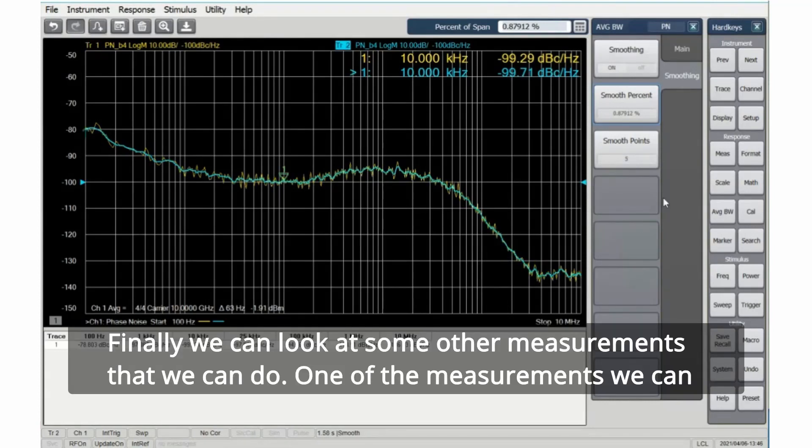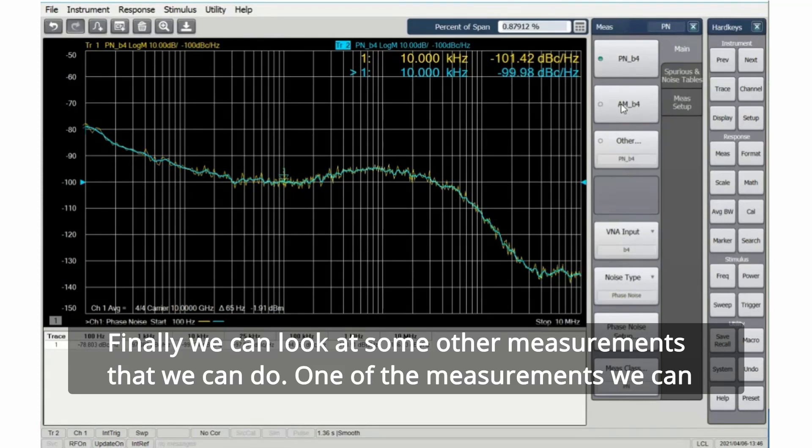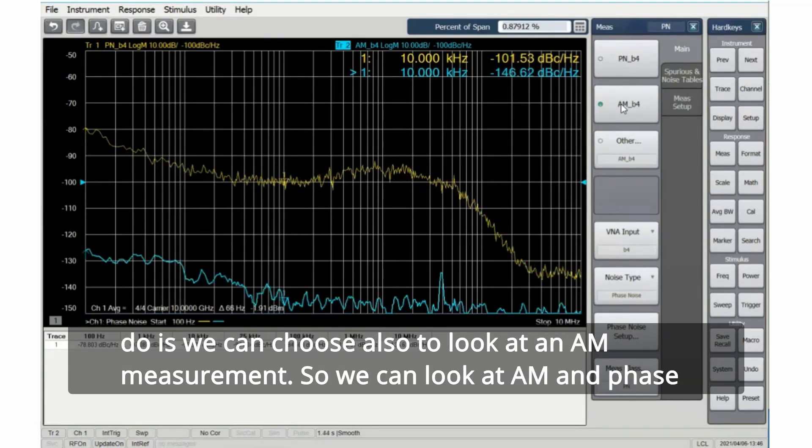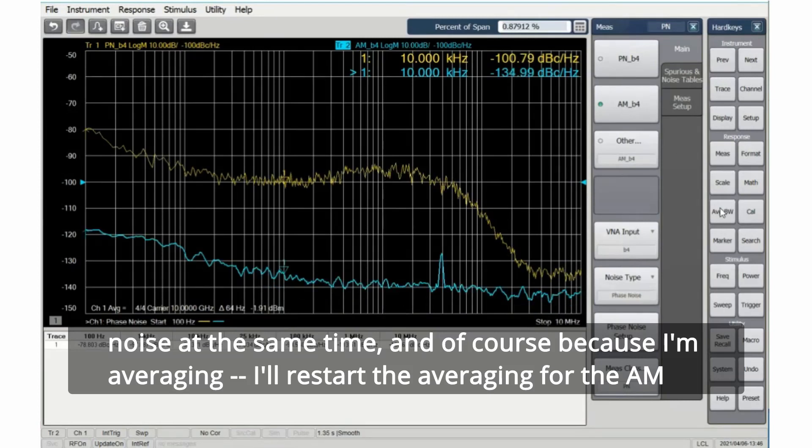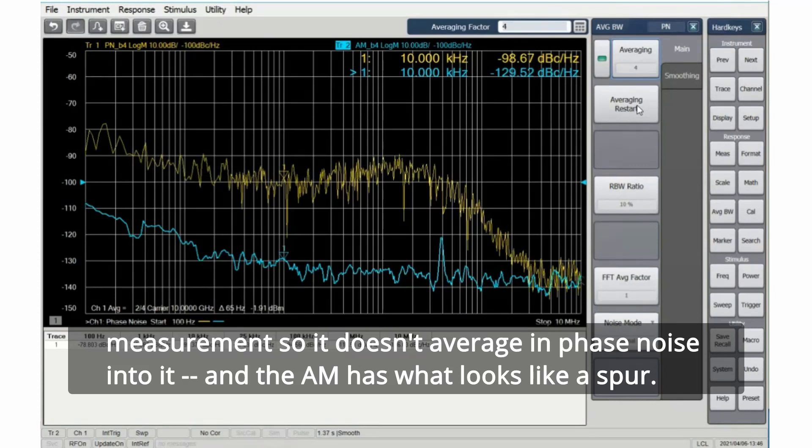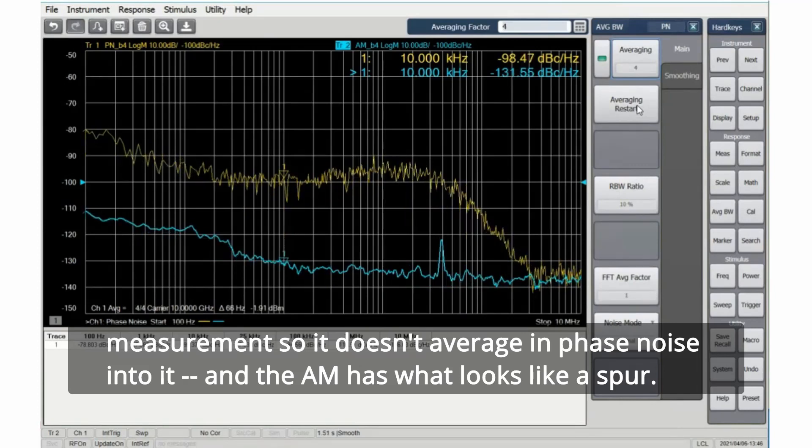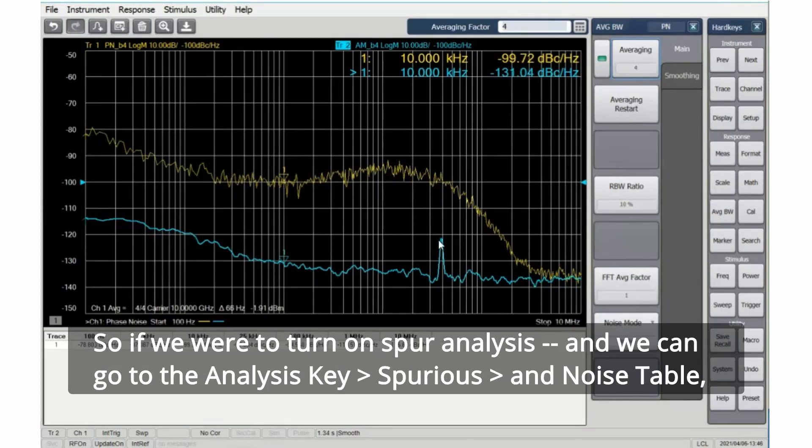Finally, we can look at some other measurements that we can do. One of the measurements we can do is we can choose also to look at an AM measurement. So we can look at AM and phase noise at the same time. And of course, because I'm averaging, I'll restart the averaging for the AM measurement so it doesn't average phase noise into it.